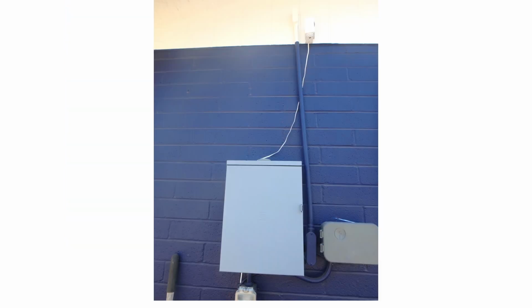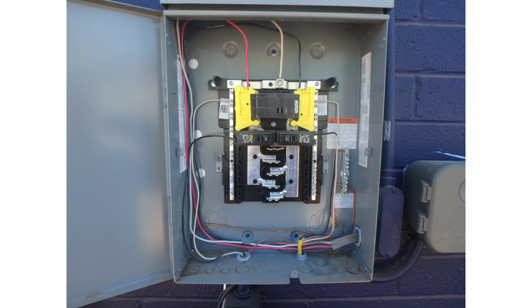And now, when you get to a sub panel, you can tell on this one where the electric is coming in. Check out the box itself. We're going to open it up. Again, dead front panel, front side, back side. On the interior, we're going to follow that electric as it comes into the panel to the main bus, down the bus bars. Check out the breakers, compatibility, follow the conductors as they leave the panel, eventually coming back out on the neutrals and then the ground.